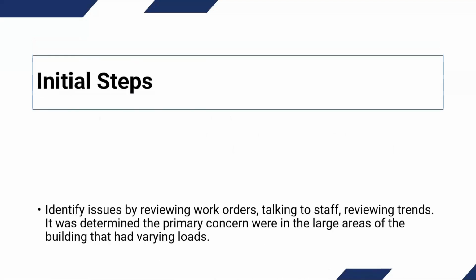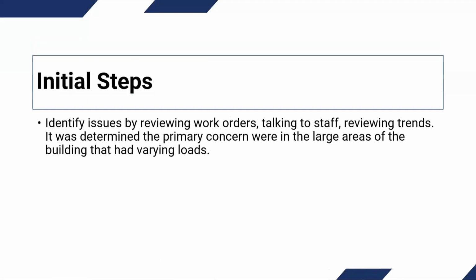So again, our initial steps are the same on every project. We looked at work orders, we talked to staff, we looked at trends, and like they told us, the primary areas of concern were the large areas that had varying loads, like the libraries or the gym, where you could have 10 people or you could have 150 people. Went through the same procedure. We always take measurements on any problem project. So we measured all the rooftop units, total CFM, ran them through our paces, took temperatures, verified all the sequences of operation on all the equipment, ran them through their procedures.